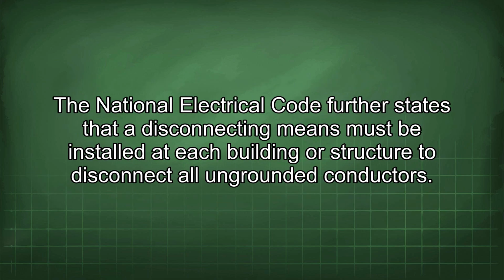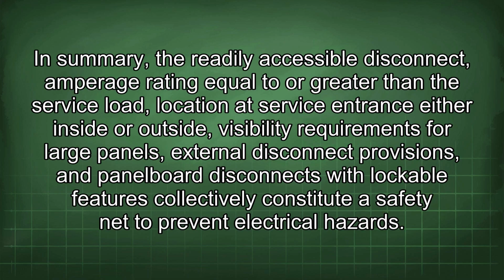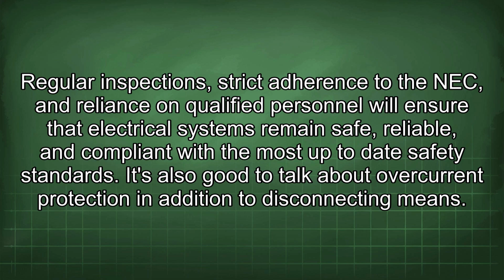The National Electrical Code further states that a disconnecting means must be installed at each building or structure to disconnect all ungrounded conductors. In summary, the readily accessible disconnect, amperage rating equal to or greater than the service load, location at service entrance either inside or outside, visibility requirements for large panels, external disconnect provisions, and panel board disconnects with lockable features collectively constitute a safety net to prevent electrical hazards. Regular inspections, strict adherence to the NEC, and reliance on qualified personnel will ensure that electrical systems remain safe, reliable, and compliant with the most up-to-date safety standards.